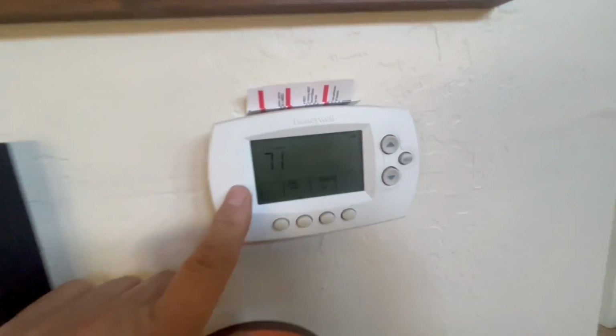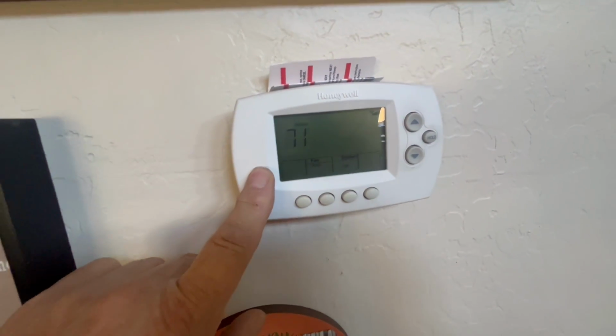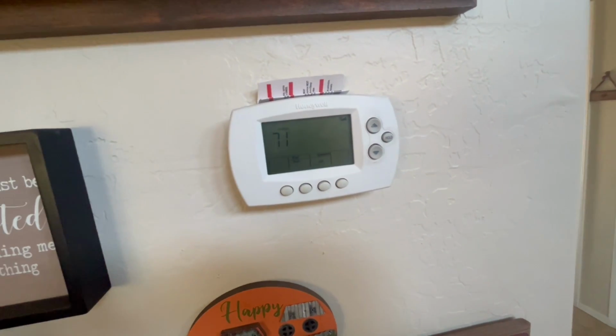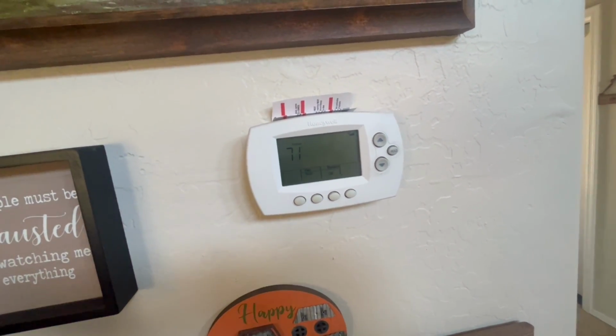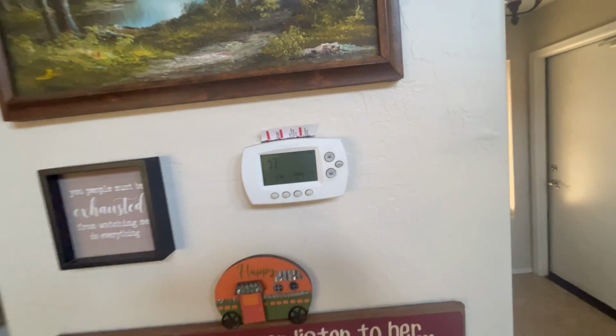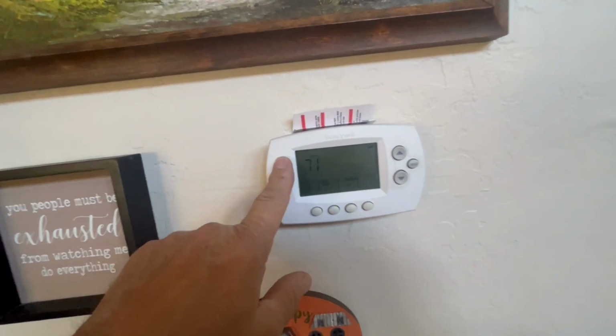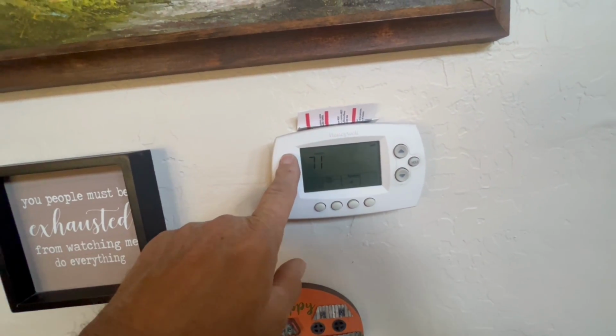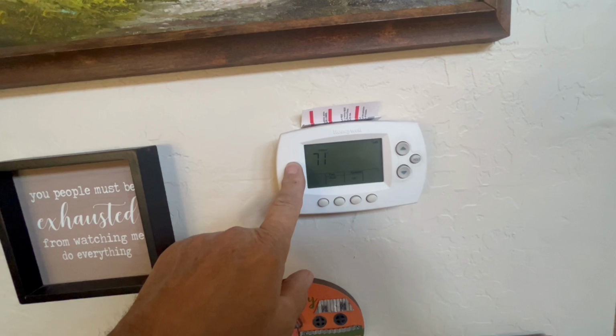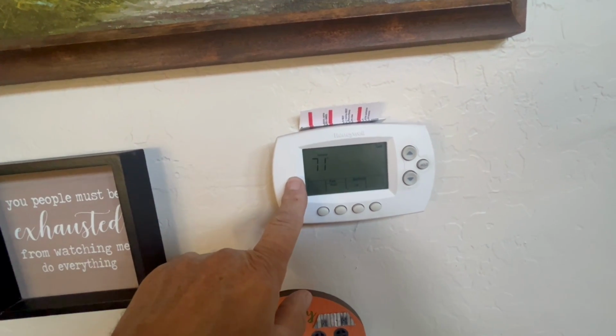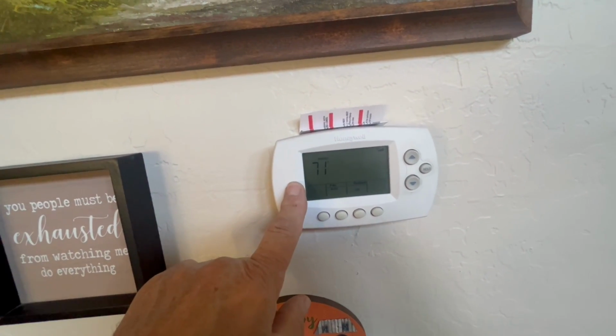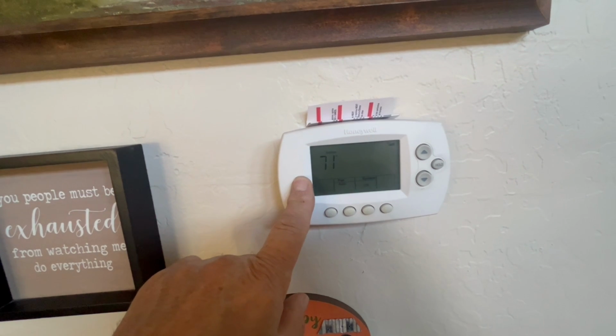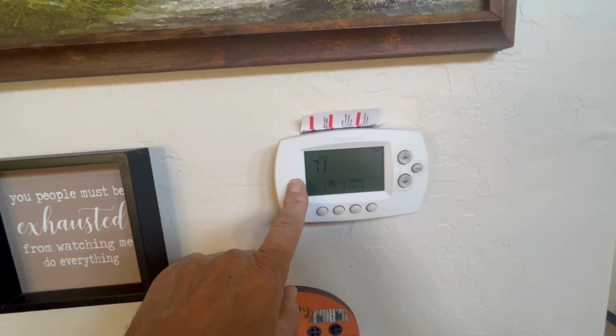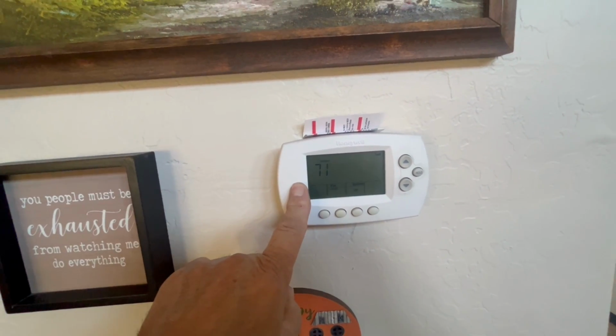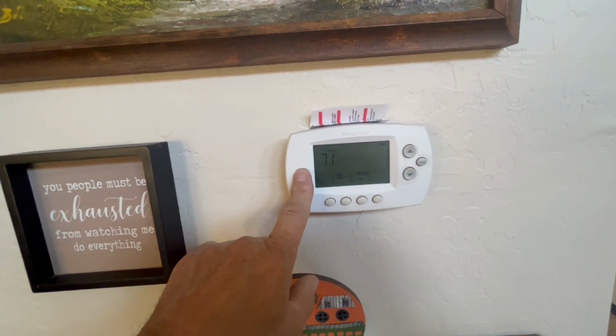Now, my main air conditioner, once this thermostat reaches the temperature desired that you have it set at, it just shuts off the air conditioner or the heating. And the problem with this is I had to put a soft start on these things on the upstairs and downstairs to get them to work. This one pulls 119 amps startup surge on the amps. And I got it down to like 32 to 36 amps by putting a soft start on it.